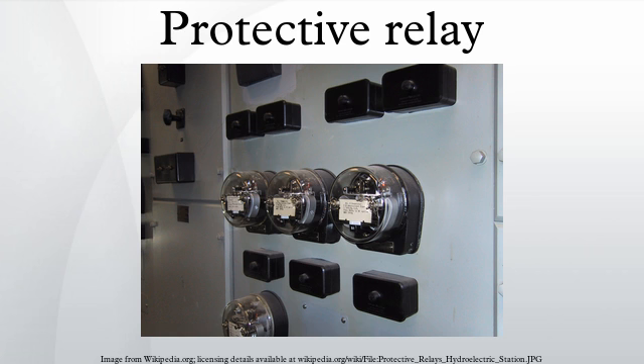The rotary motion of the disk operates a contact. Induction relays require alternating current. If two or more coils are used, they must be at the same frequency, otherwise no net operating force is produced. These electromagnetic relays use the induction principle discovered by Galileo Ferraris in the late 19th century.